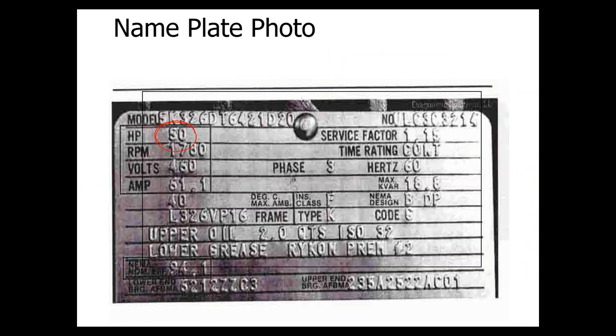This is the size of the motor, this is the RPM. You can see voltage, you can see service factor. We're going to go through all these terms in a minute. Some other things: types of design, maximum kVAR, etc. Know that you can find these things on the nameplate. Most of the time the nameplates are embossed because they often get painted, there can be grease or dirt, and the embossing helps you see the numbers on the motor.